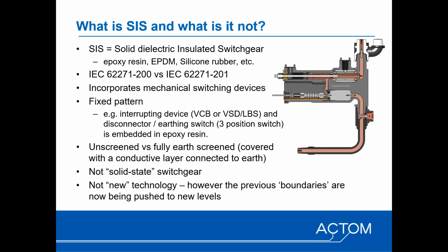By now, I'm sure you've realized that SIS stands for solid dielectric insulated switchgear, and the solid dielectric insulation could be epoxy resin, but it could be alternative materials such as EPDM, silicone rubber, and so on. To some degree, we might have already been exposed to some solid dielectric switchgear insofar as the bus bars on some fixed pattern switchgear. Some bus bars are effectively solid dielectric and fully screened, although they are then used in combination with GIS switchgear.